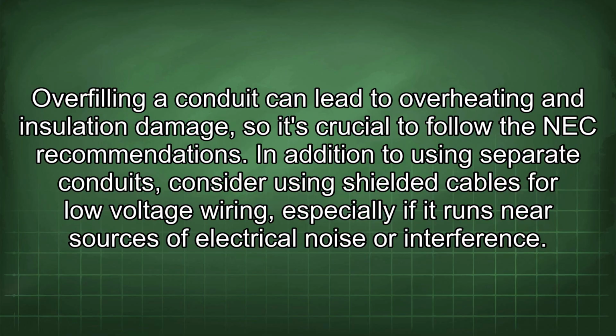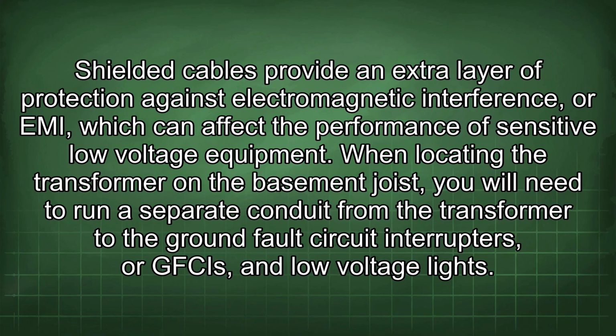In addition to using separate conduits, consider using shielded cables for low voltage wiring, especially if it runs near sources of electrical noise or interference. Shielded cables provide an extra layer of protection against electromagnetic interference, or EMI, which can affect the performance of sensitive low voltage equipment.